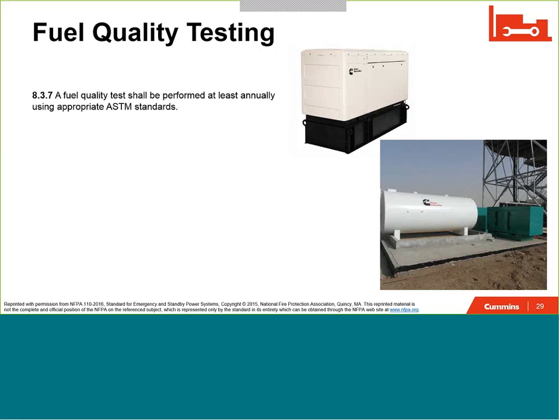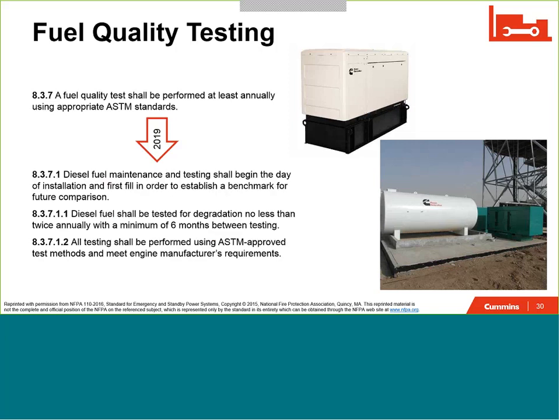However, the other key thing to keep in mind here is the capability of that testing and what that testing is telling you. Actually, there's a temporary interim amendment in the works right now that is going to expand the requirements for fuel quality testing in 2019, and I included just a few details from that TIA, and it goes on into much greater detail. In fact, it's a couple pages long as opposed to the standing requirement today. So this is just something to be aware of and look forward to as we move towards the adoption of that TIA.